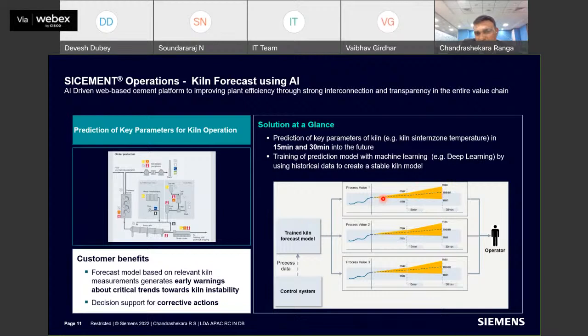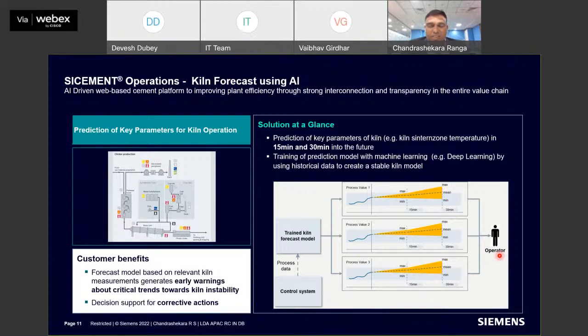What is the advantage of forecasting these key parameters for the operator, right? The operator has a fairly good amount of time to bring the out-of-control parameters into range, and he can stabilize the whole process. By stabilizing the process, he's burning less fuel, using less oxygen supply, and producing less CO2 emission. So it also gives early warning and indication.